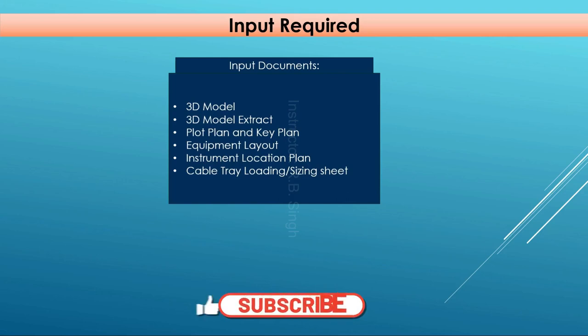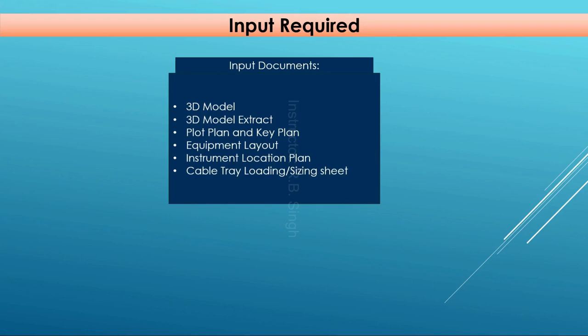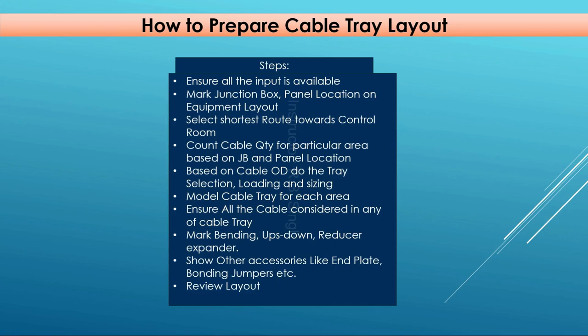By this way we can prepare the cable tray layout in AutoCAD. But if you have a 3D model and have already modeled the cable tray in 3D, this manual workout is not needed — you can just extract the 3D model and the layout will show there. You just need to mark the cable tray number and route number, prepare the legend sheet, and show the key plan, and your layout is ready. Otherwise, the manual process using the instrument location plan must be followed. By both ways you can prepare the main cable tray layout.